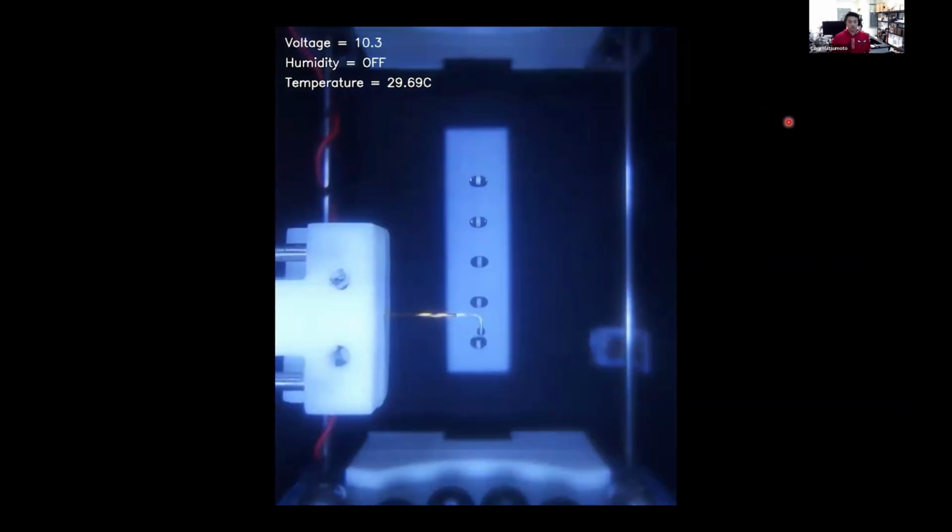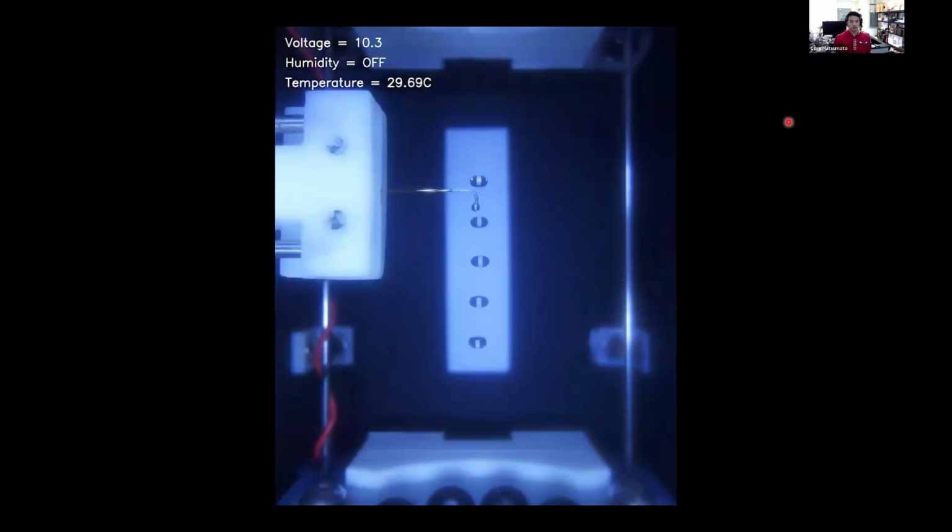So after our incubation steps, we'll get addition of reagents, and this is actually contactless addition. So a reagent droplet forms, which only touches that sample droplet. The capillary never touches. So this is to prevent cross-contamination as well as any loss to that capillary tip. And so we do this by identifying and mapping out the precise coordinates of that capillary tip as well as the levitated droplet utilizing computer vision, as you can see to the right.